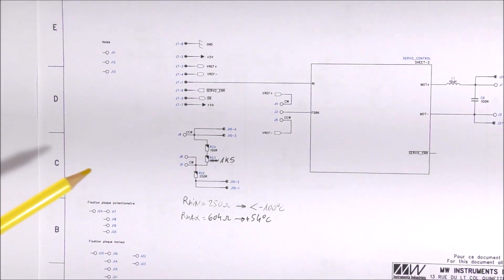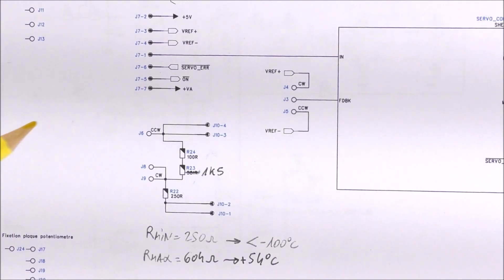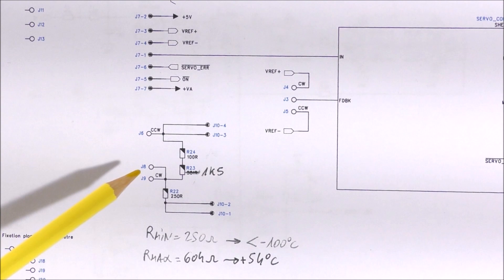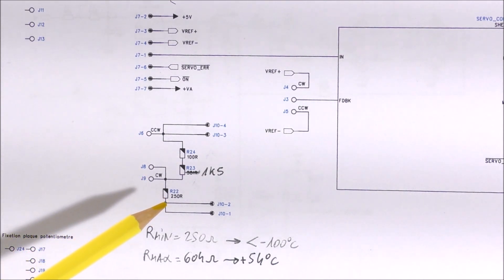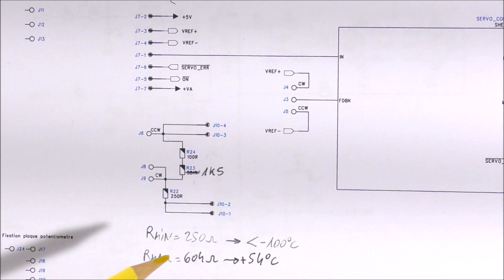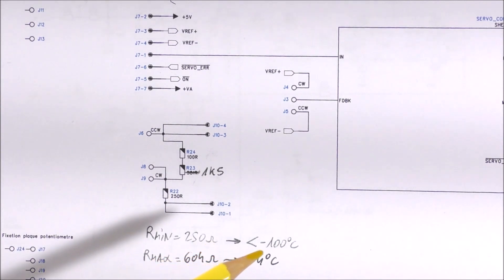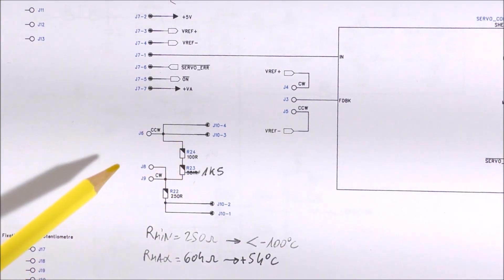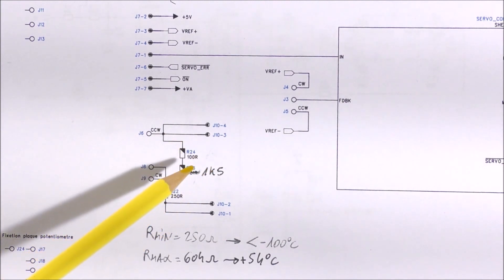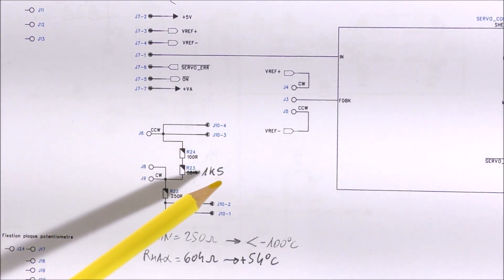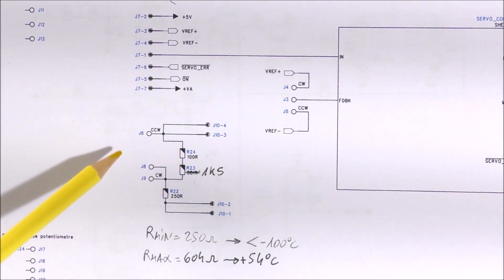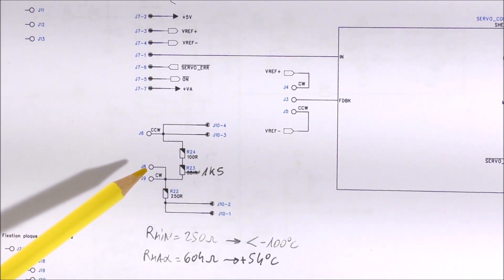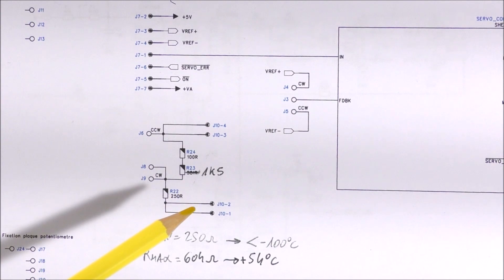The potentiometer used for the sensor is a 1K potentiometer plus or minus 3%. There will be an accurate resistor in series at 0.01%, which permits to have a minimum temperature below minus 100 degrees. And there will be a resistor in parallel to the potentiometer — 1K5 plus 100 ohms at 0.01%. The actual value of the potentiometer will be measured and entered in the firmware in order to set the exact resistance value according to the temperature.